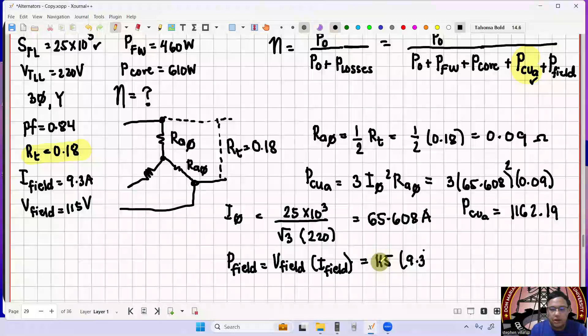Okay, let's get the field copper loss. This is equal to your voltage in the field multiplied by your current in the field. This is now equal to 115 multiplied by 9.3, so that is 115 times 9.3, which is now equal to 1069.5. Okay, that's done.